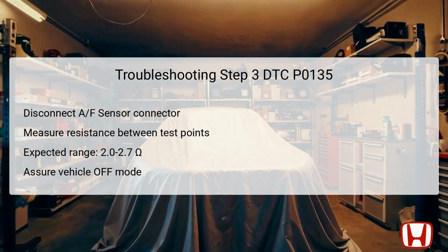This measurement is essential because it reflects the condition of the internal heater within the sensor. If the resistance falls outside this range, it suggests a malfunctioning sensor, necessitating its replacement. Understanding the significance of these measurements can help in quickly pinpointing sensor-related issues.